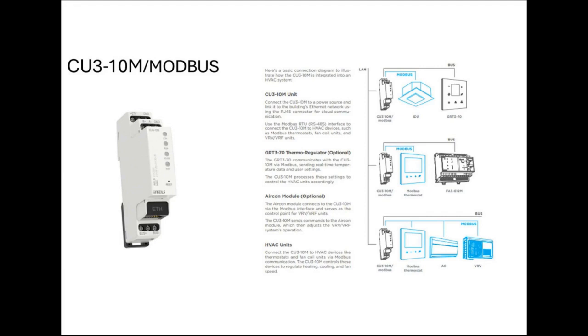In the next slide, I will show you how you can use it. But first, I will discuss different methods where you can control the CU3-10M through the Modbus protocol. So in the first diagram, you can see that the CU3-10M is connecting directly to the indoor unit using the Modbus cable. So in this way, you can use our GRT3-70 to set the temperature and then eventually turn on this Modbus. What you need is the Modbus register table for this indoor unit fan coil, and then, using the GRT3-70 as a controller, you can set different parameters to turn on the Modbus. So this is case one.